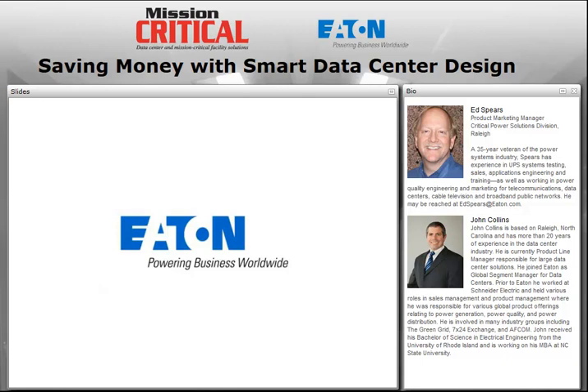Yeah, and that's a great point, Ed. I don't want it to be lost on the answer that you want your control system to look at the actual load of the UPS, not what the UPS is rated at, because we all know that UPSs are typically never fully loaded, especially in a redundant system. And so by looking at the actual load, you'll be able to have more of the primaries able to be backed up in the event of an emergency. Exactly.